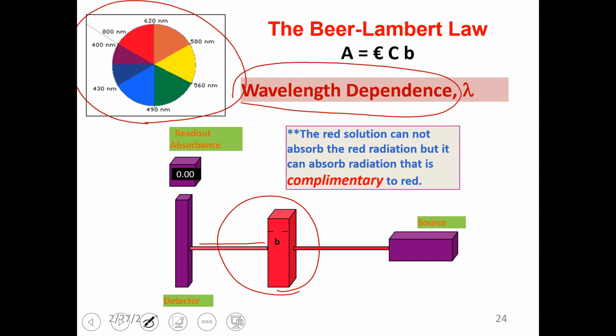So you have to choose the color which is complementary, or opposite on the diagonal, to that of the color wheel. So generally we divide the color wheel into six components, and one component of the six will be again divided into 2, because there is not much difference between violet and indigo. You all can recall VIBGYOR here. So each color has its own unique wavelength range. You can infer from the color wheel. And suppose the color of your solution is red, you have to choose the green filter, that is opposite or diagonal to the color. Suppose your color is blue, then you have to choose the wavelength which is diagonal towards orange. Suppose your color is violet, you have to choose yellow.